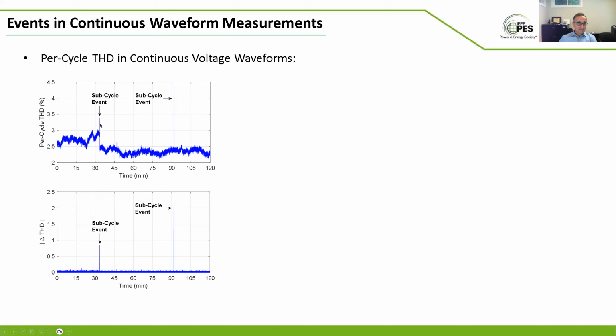But you see, total harmonic distortion jumps up a little bit here and jumps up a little bit here, okay? Or if you look at the change in total harmonic distortion, there is a big step here and a good step here. If your total harmonic distortion has increased, that implies there is a disturbance in the waveform. If your waveform was purely 60 hertz or 50 hertz and no noise, your total harmonic distortion would be 0, okay? With some noise and some harmonics, you have some base total harmonic distortion, okay? But when you have a little step up in a short time, it usually means a waveform disturbance.